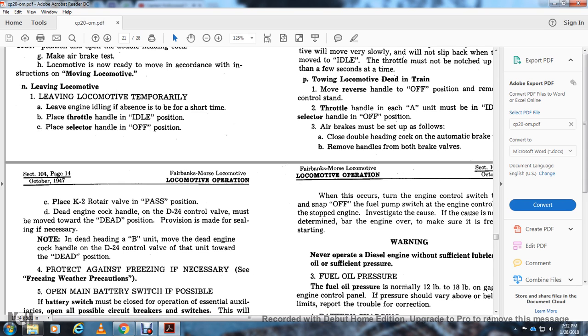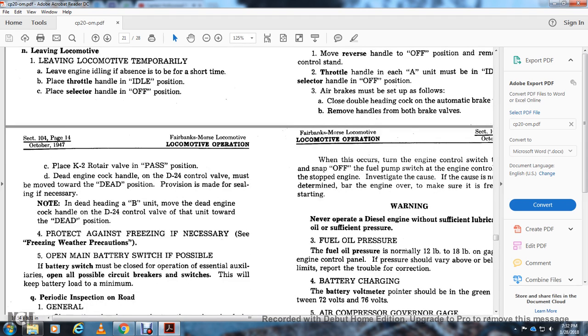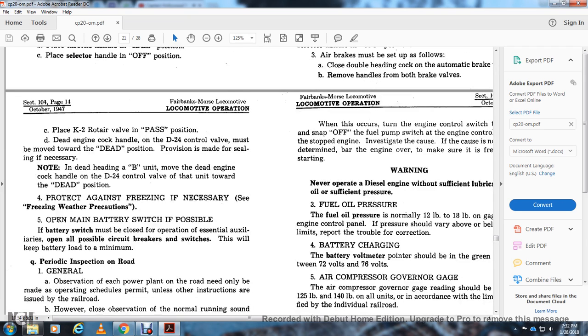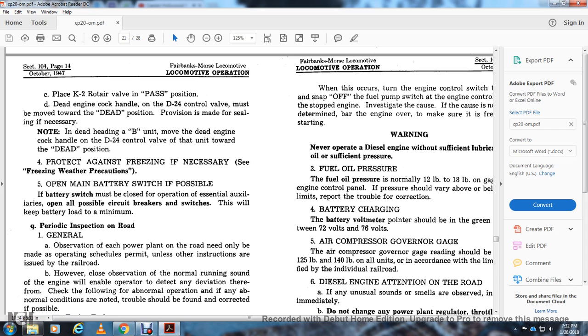See the freezing weather precaution. Open the main battery switch. If battery switch must be closed for the operation of essential auxiliaries. Auxiliary: open all the possible circuit breakers and switches. This will keep the battery load to a minimum. Periodic inspection on the road and general observation of the power plant need only be made as operating schedules permit, unless other instructions are issued by the railroad.